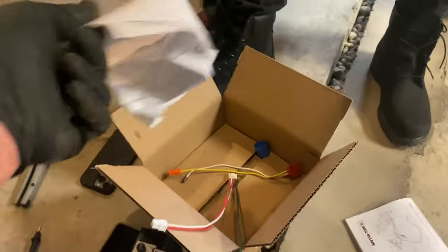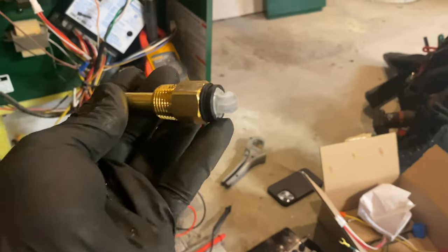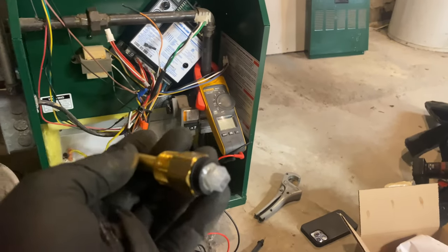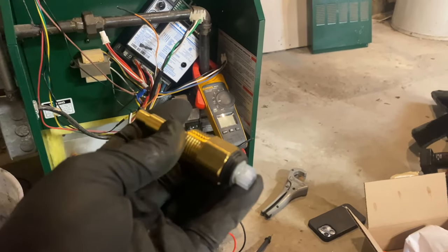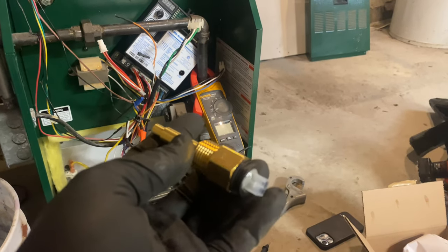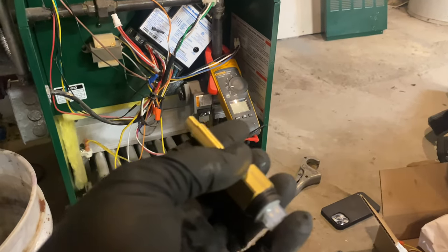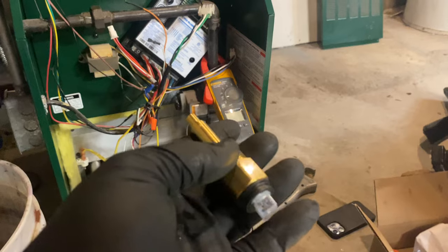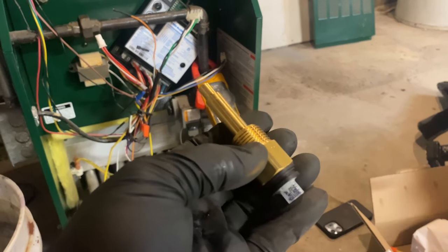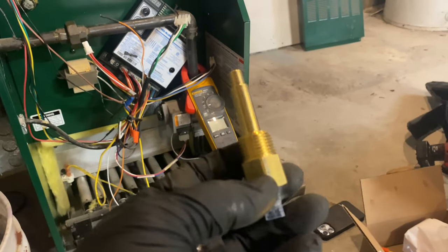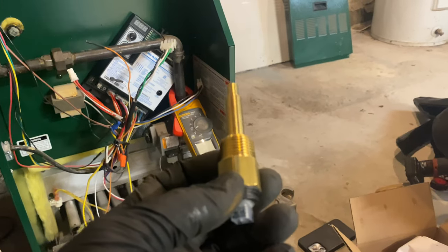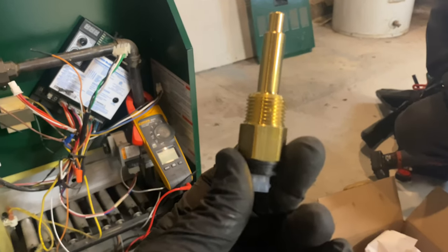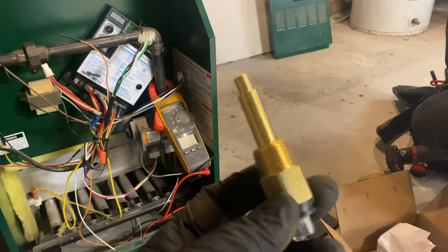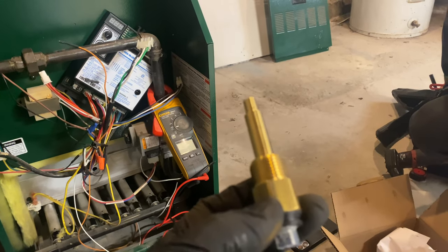It doesn't say in the manual here that came with this little thing, the instructions. There's no instructions that come with this. However, there are instructions that come with a Guard Dog RB-24 low water cutoff, and there's also instructions that come with a steam boiler low water cutoff. And it says on those instructions, do not use PTFE tape on the threads of the probe that's going inside the boiler. You shall use some kind of paste-based sealant, which is what we're going to use.